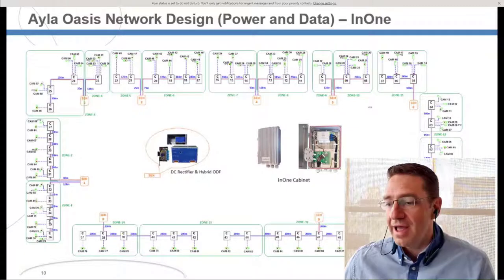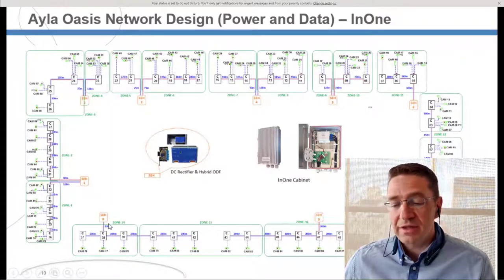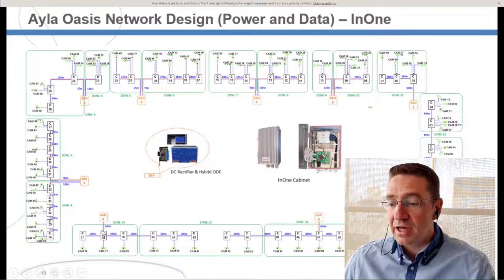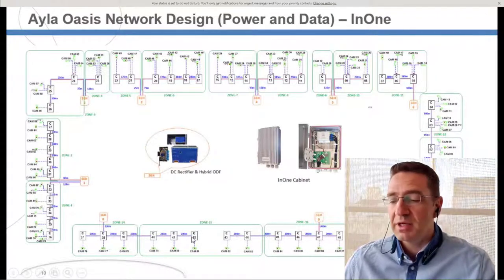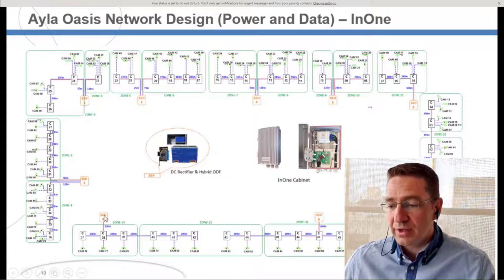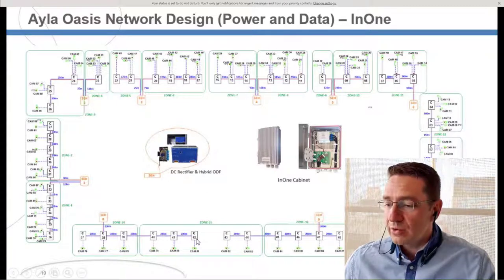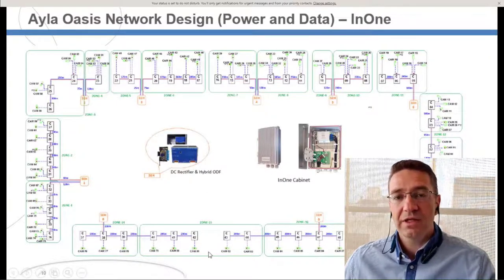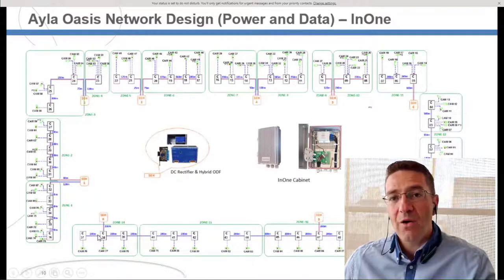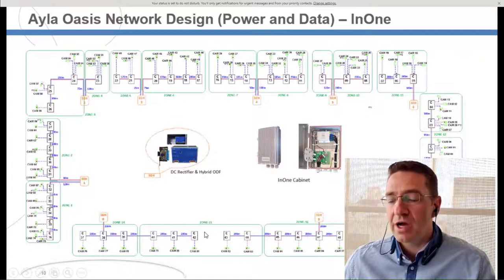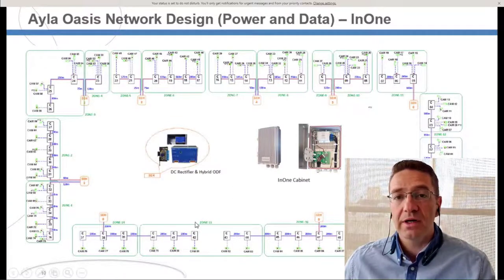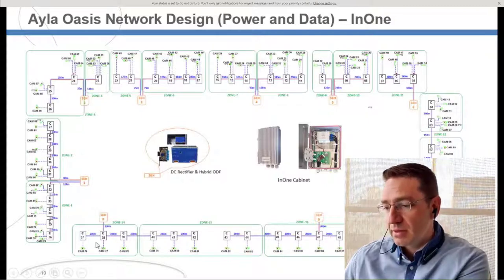It's not a test or anything — it's really implemented. So you see we can reach long distances while serving a lot of cabinets, because each of these cabinets actually has only one camera. That's why we could reach this distance, but I'll speak more about that. In total, you can reach around 1,000 meters while serving 6 different cameras on the road, each 200 meters from the next. Just see how much you save here in power and civil work compared to doing this the traditional way.